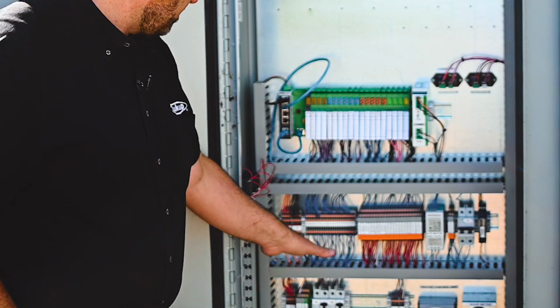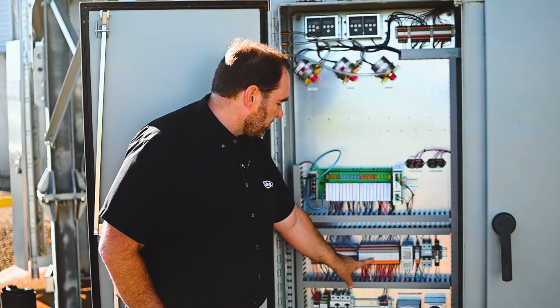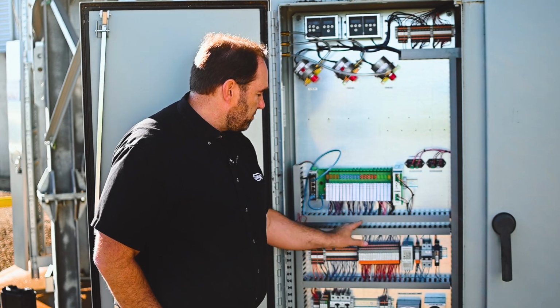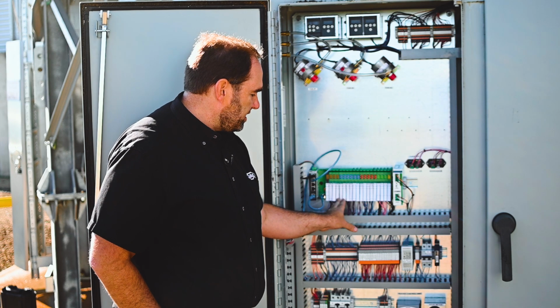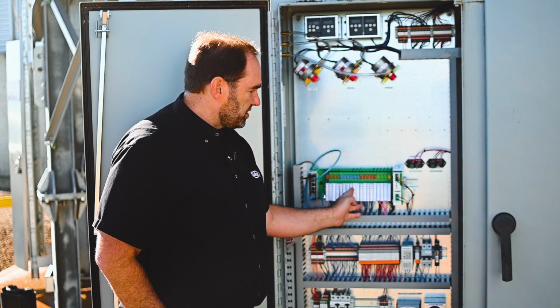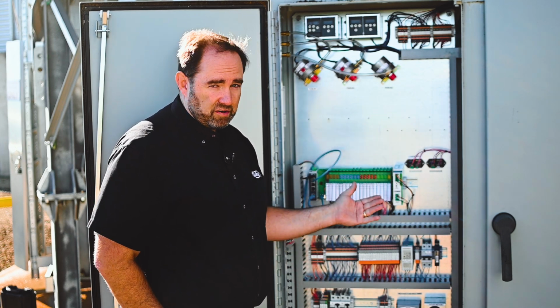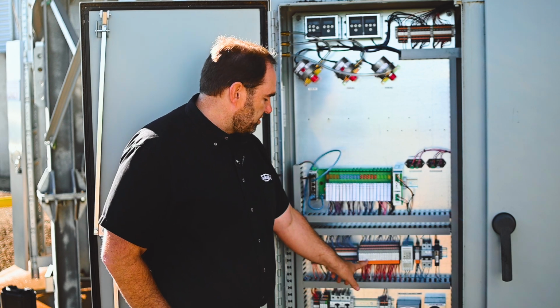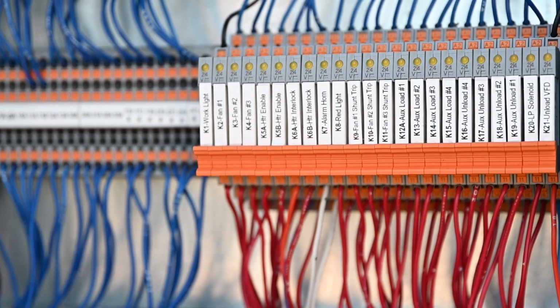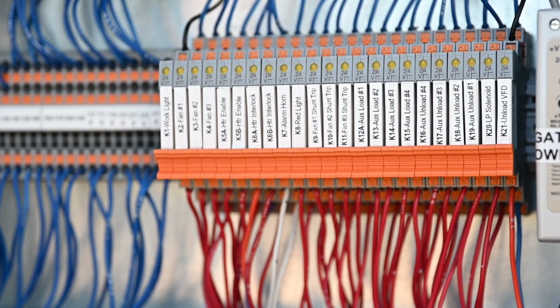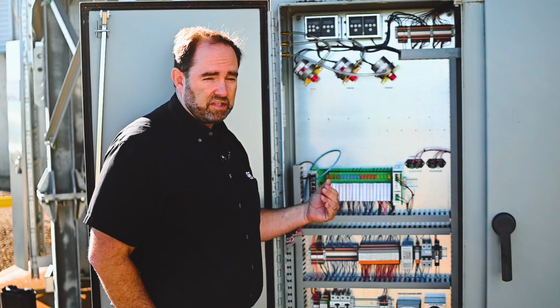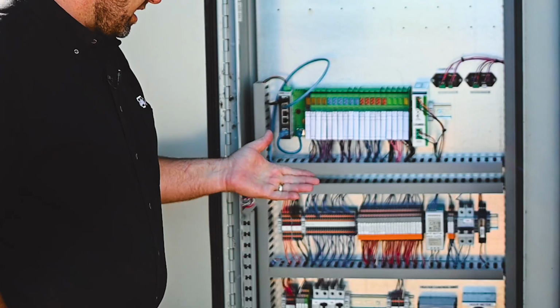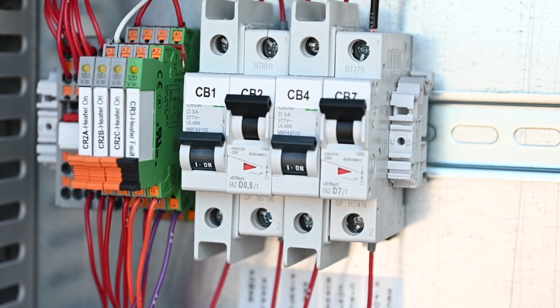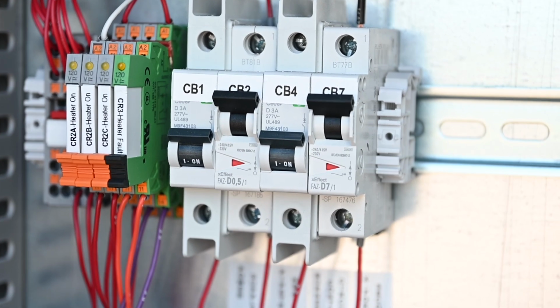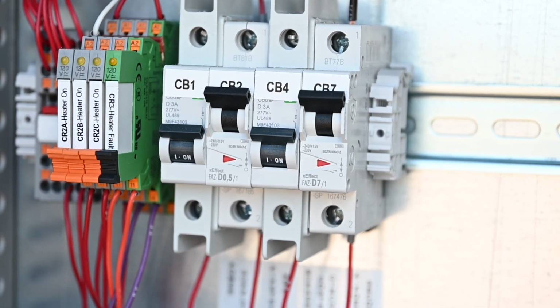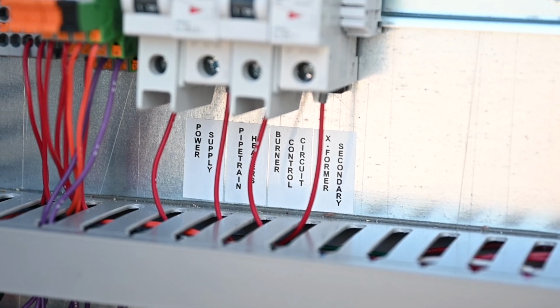Just keep coming down. We've got terminals here, and then these are relays. And so I mentioned the PLC works off of 28 volts DC. Well, if the PLC wants to start a fan, that's going to need a 110 volt signal. And what these relays do is translate 28 volt DC into 110. And there's a number of them for the fans, for the unload, for the auxiliary load and unload equipment, and the heater as well. Come down a little lower, we've got some more relays, circuit breakers. Just note up is on, so you want all those breakers in the up and on position.